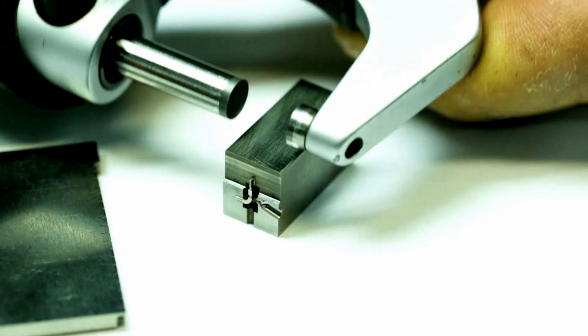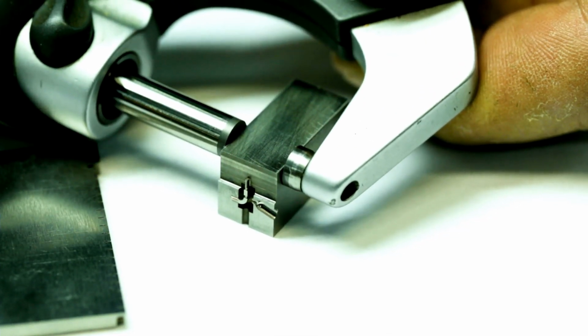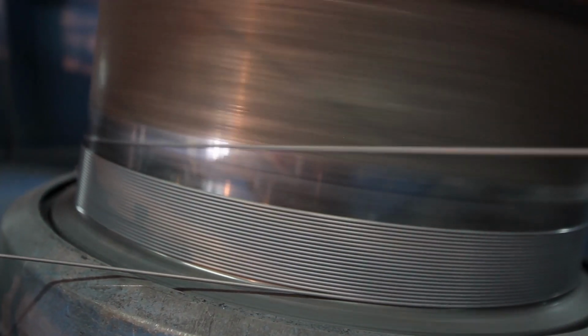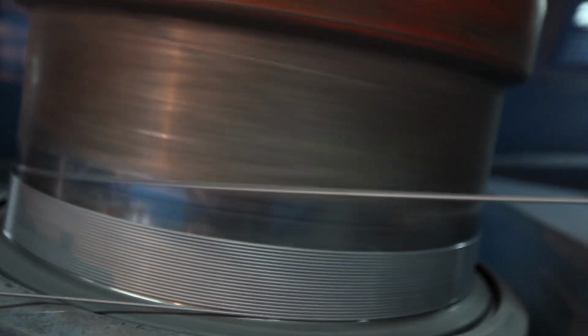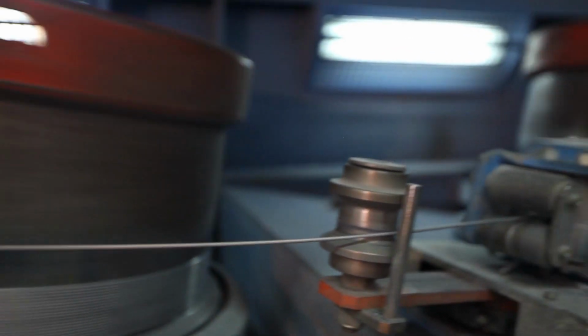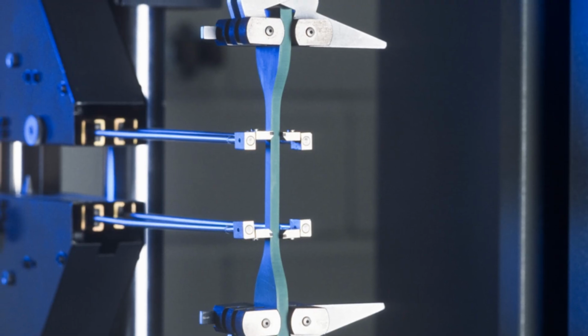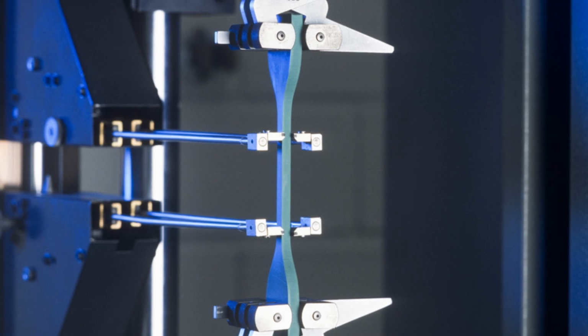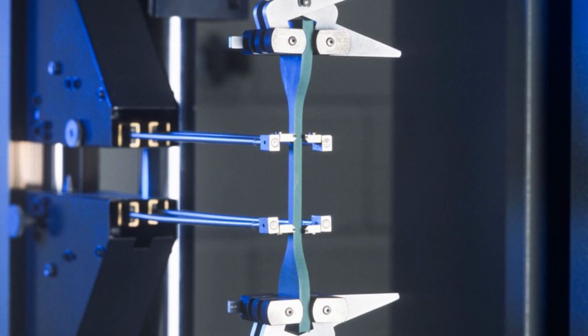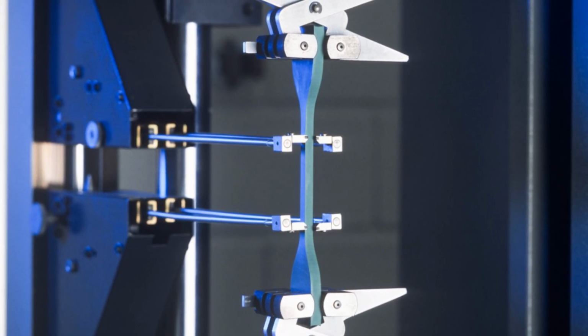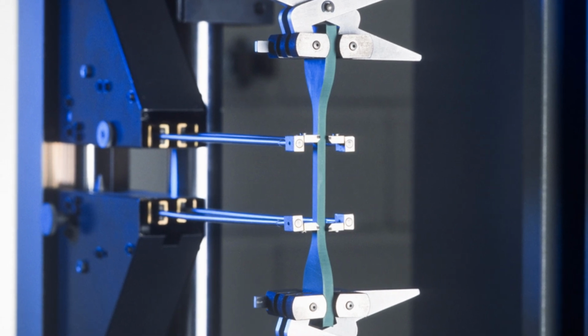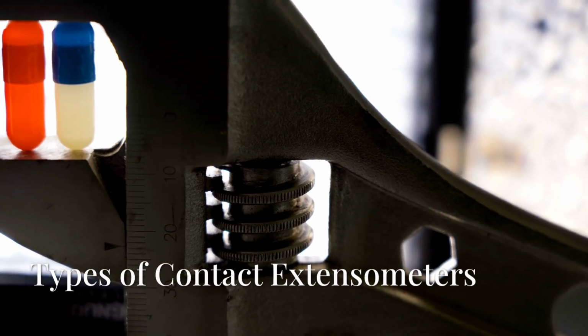For example, very thin specimens such as foils can be sensitive to clamping forces, and small wire specimens may not provide enough visible area for reliable non-contact measurements. Similarly, the testing of very stiff or highly plastic materials often requires the use of a specially designed extensometer, which has been developed to resist these forces.